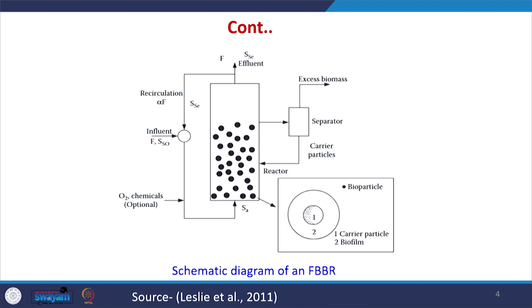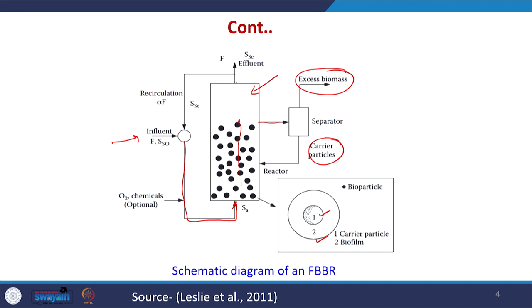This is the schematic diagram of a fluidized bed bioreactor (FBBR). The influent comes from here and goes from the bottom of the reactor inside the fluidized bed. The fluidized bed contains the bioparticles, shown as dark circles, which essentially consist of a carrier particle on which a biofilm is grown. Once the water passes through the system and treatment happens, a separator unit separates the carrier particles and excess biomass. The carrier particles are recycled back into the reactor to maintain the required concentration of bioparticles, and the treated effluent goes out from the top.